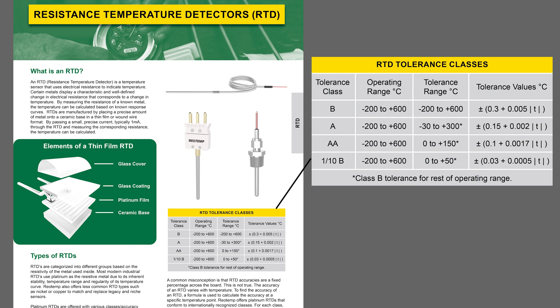This chart shows the tolerance range for each class of RTD. Let's look at the class A RTD. It has a better accuracy than class B, but only between negative 30 and 300°C. Outside of that range, it reverts back to a class B accuracy.